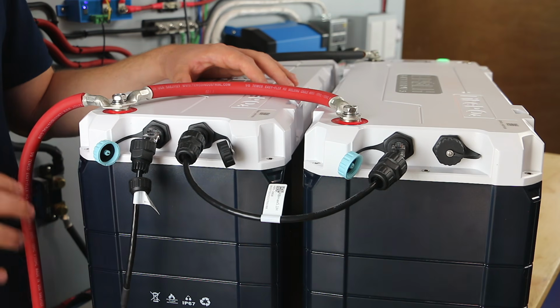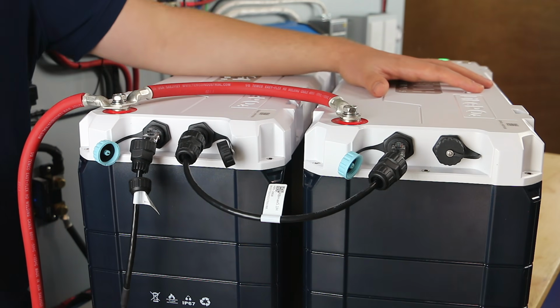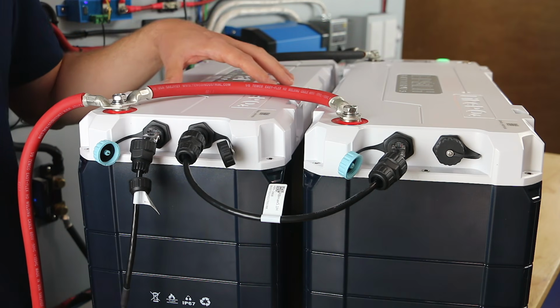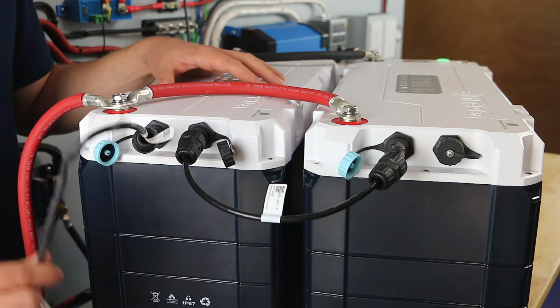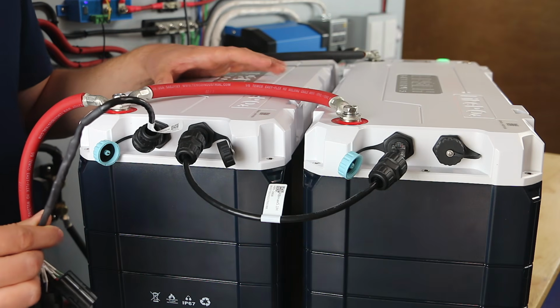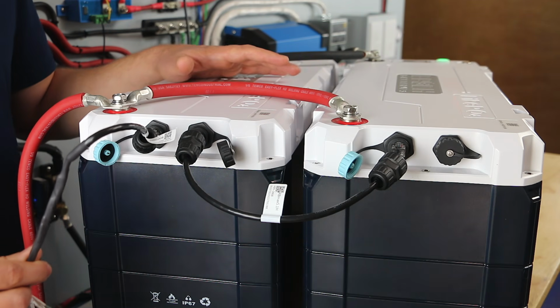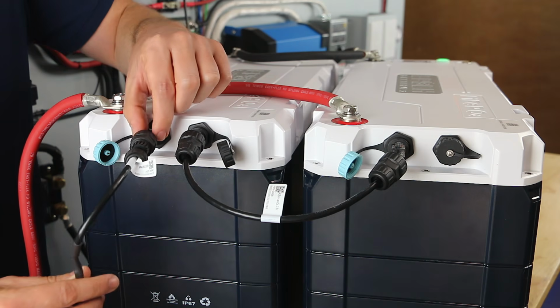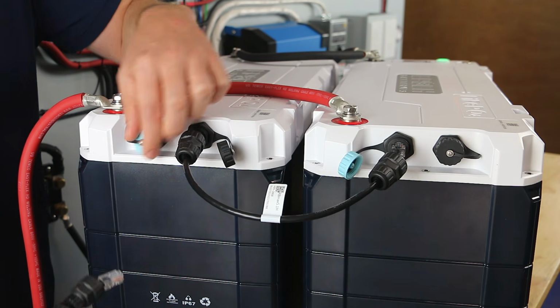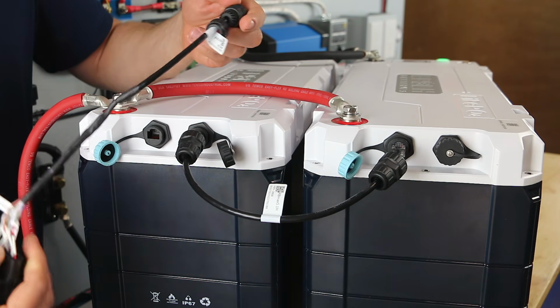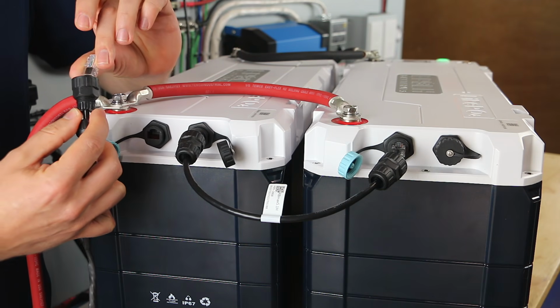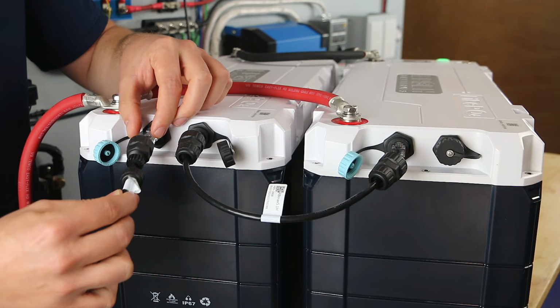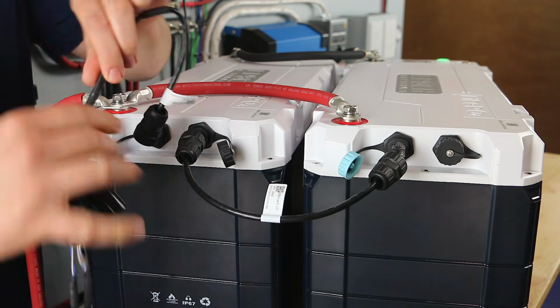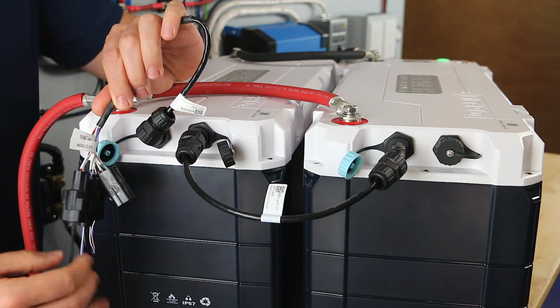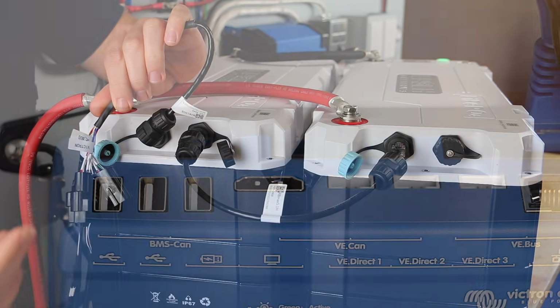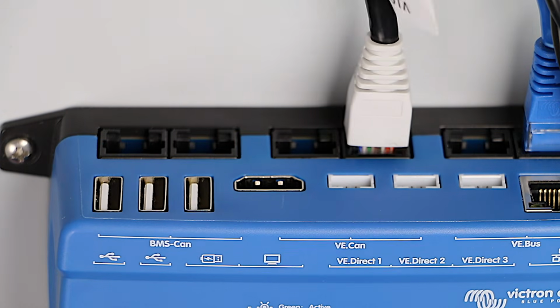In every system, you're going to have a master battery and up to 15 slave batteries. The master battery has the main wiring harness, and it reports over to your Victron Cerbo or Ekrano GX. It leaves the master battery from the blue port through this harness. The giveaway is you'll have a waterproof connector on one of the connections that goes into the battery itself. That harness then splits off in a couple directions. One of them says Victron, and that goes to the Cerbo or Ekrano GX.